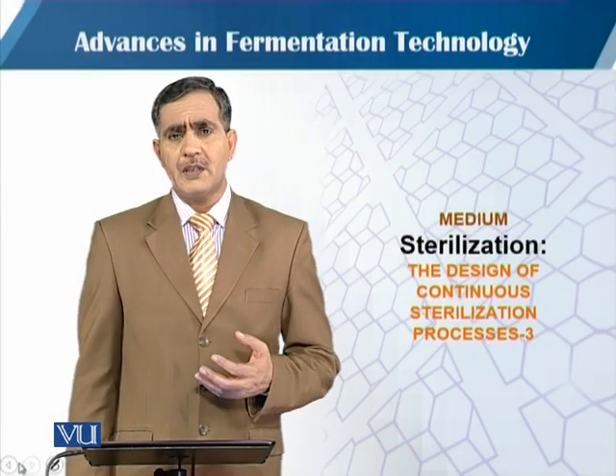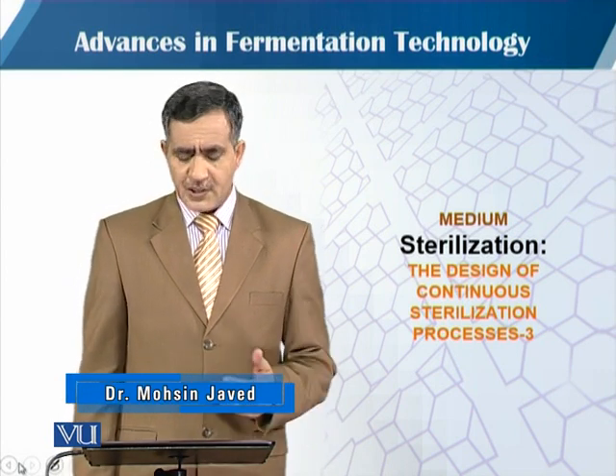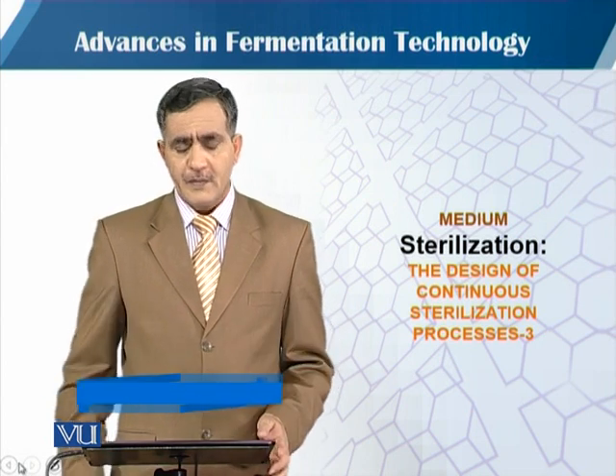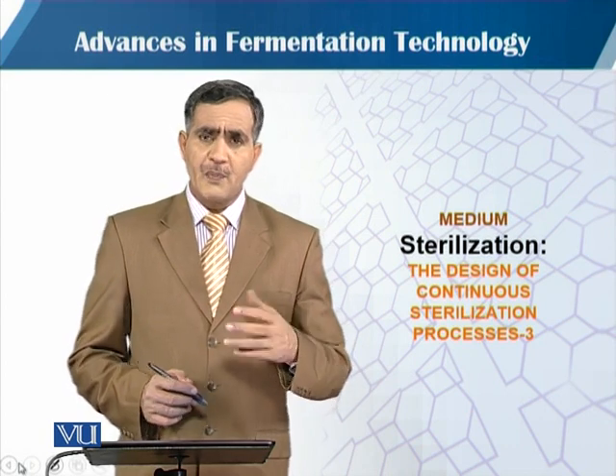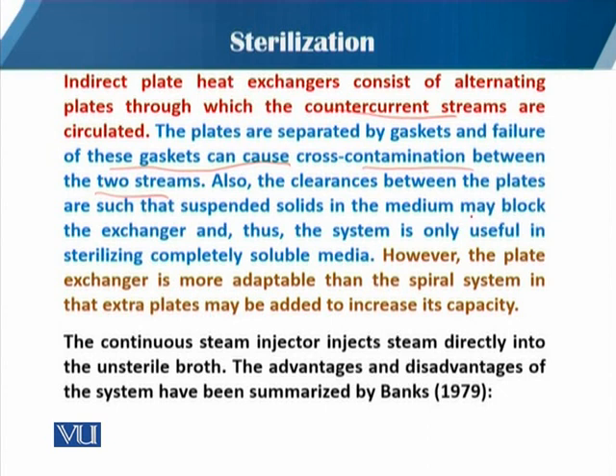In this module, we will continue the same topic as discussed in our previous module — the design of continuous sterilization, specifically the indirect method. In the previous module we talked about the spiral heat exchanger, but in this module we will talk about indirect plate heat exchangers that consist of alternating plates through which counter-current streams are circulated. The plates are separated by gaskets, and failure of these gaskets can cause cross-contamination between the two streams. Also, the clearance between the plates is such that suspended solids in the medium may block the exchangers, so the system is only useful for sterilizing completely soluble medium.